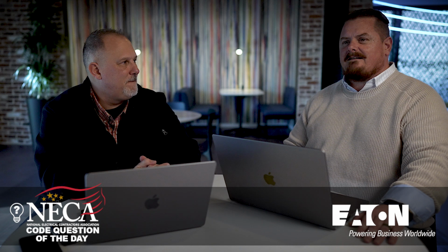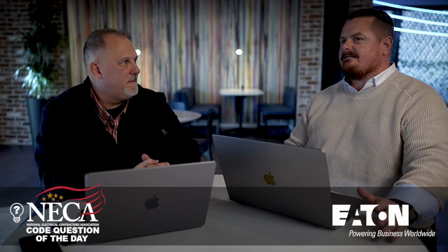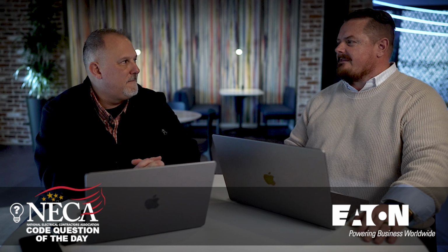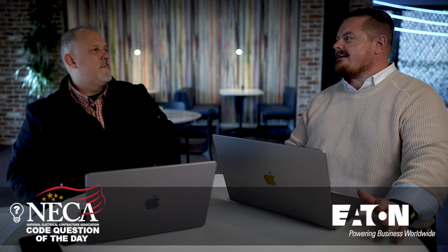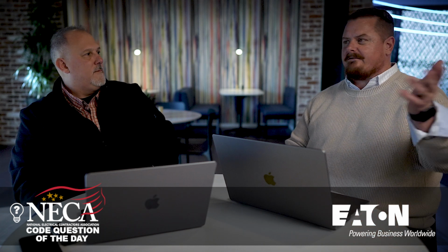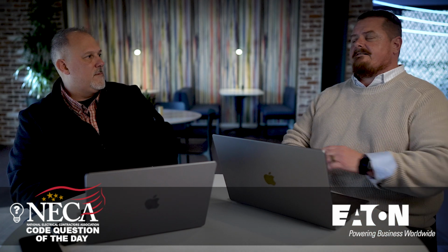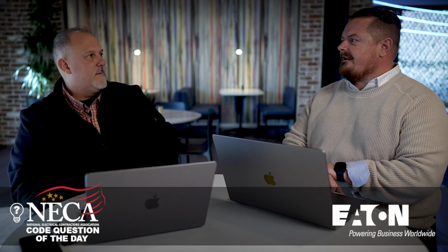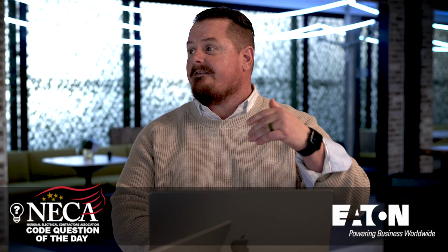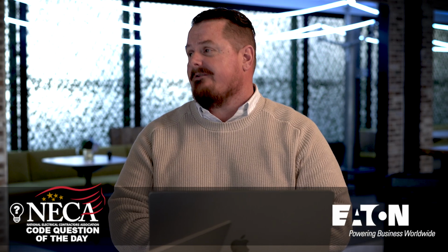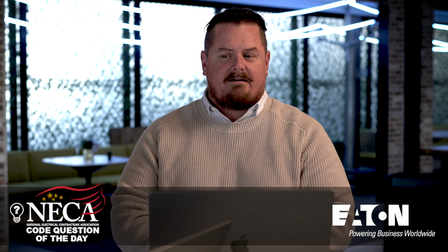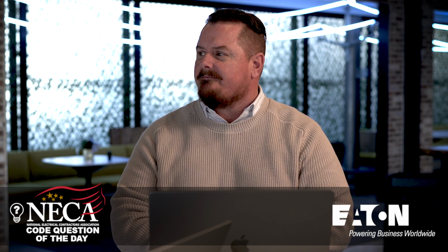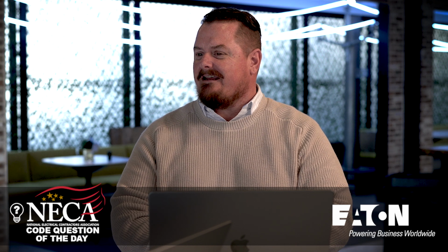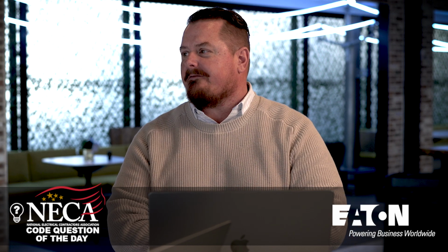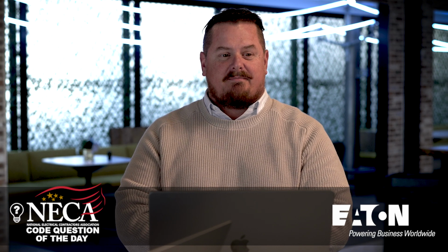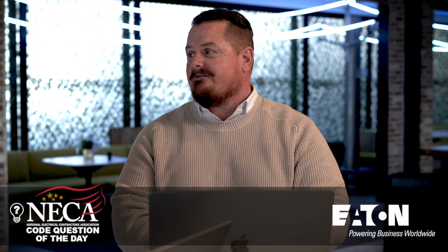Yep. So the most common question that I get is related to HVAC equipment and projects up against certificate of occupancy. There are inspectors coming through doing final. We've got new rules in the NEC, relatively new depending on where you're at, that HVAC equipment controls have to be marked with the available fault current and the short circuit current rating. And once we get down to that final inspection time, it's identified that the HVAC electrical equipment is only rated for 5,000 amps of fault current. Yep. And there is above and beyond that available at each one of those connections.